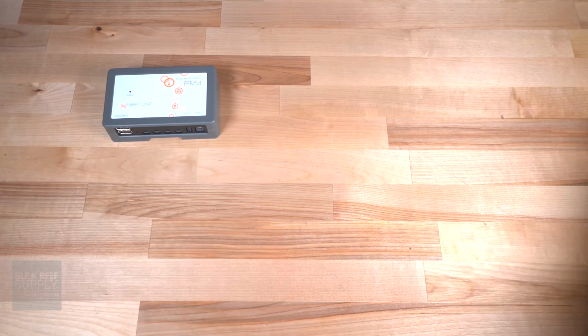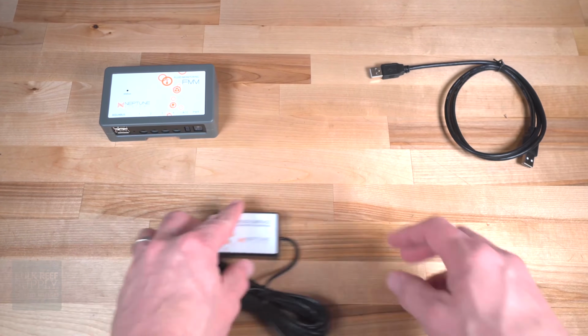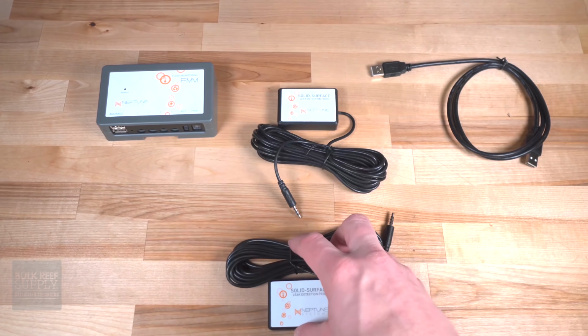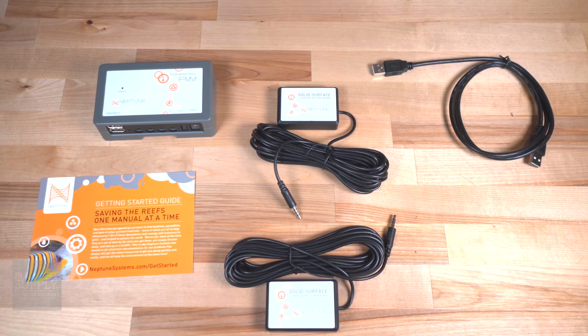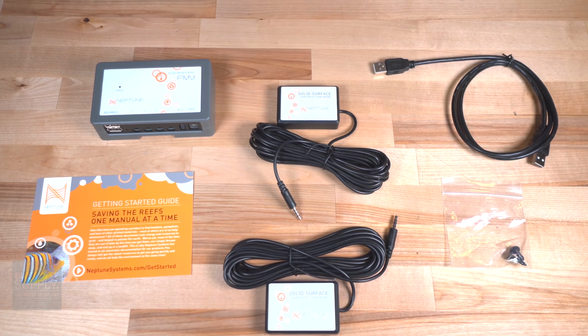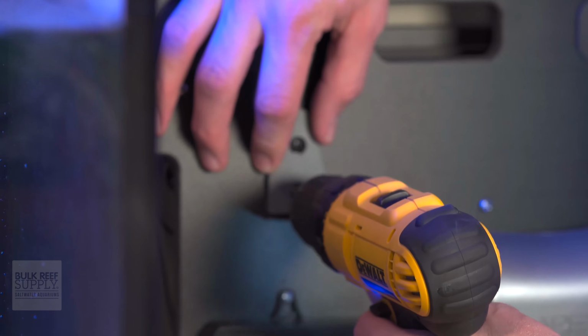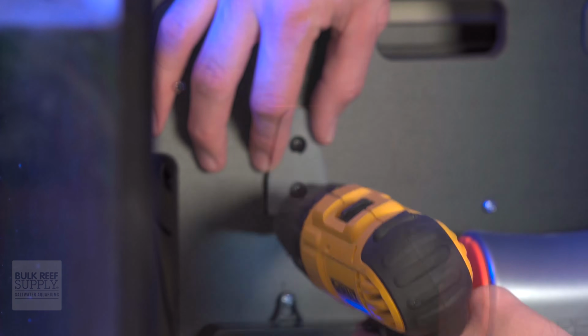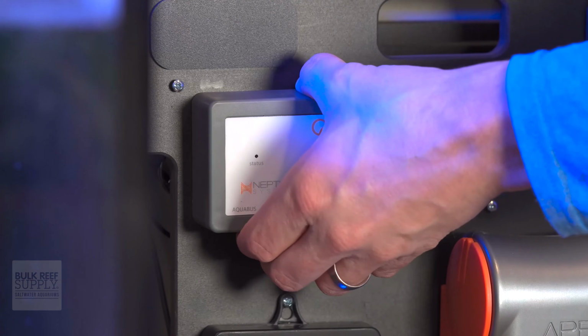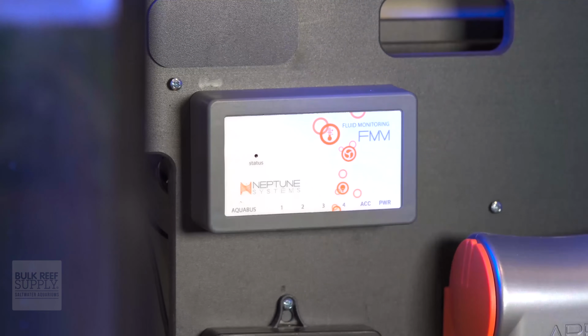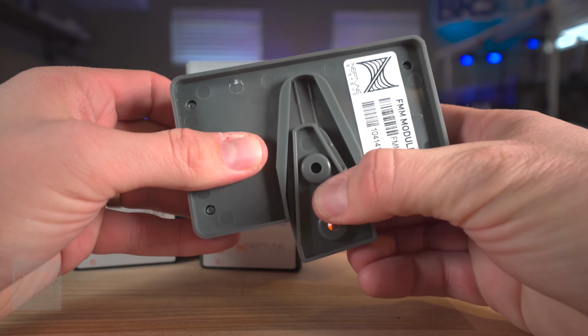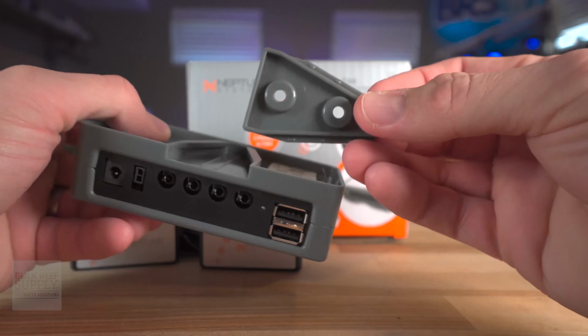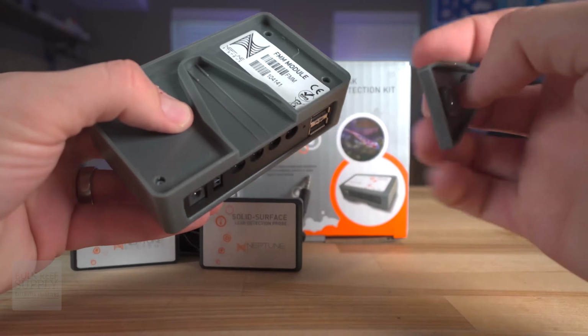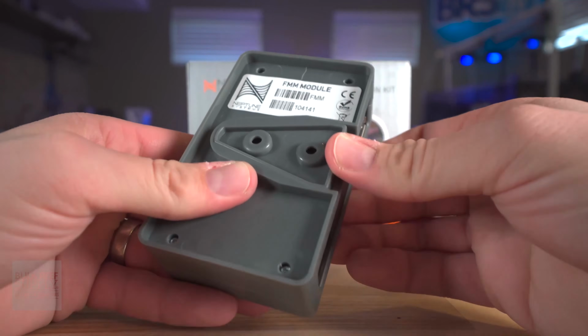In the box, you'll find the FMM, the Fluid Monitoring Module, 2 LD2 leak detection probes with 16-foot cords, a 3-foot Aquabus cable, some mounting screws, and the instructions. So once you've unboxed the module, the next step would be to mount that box to either a controller board, the inside of your tank stand, or on the outside of your tank stand. When you're mounting this, just remember to leave about a ½ inch of play above it, because if you ever want to remove it, you're going to have to lift it up and off. So you're gonna need to leave about a ½ inch of clearance from other equipment.